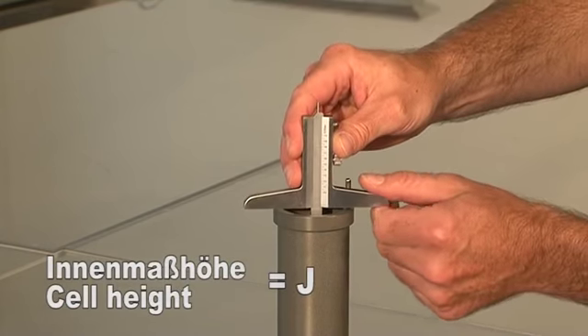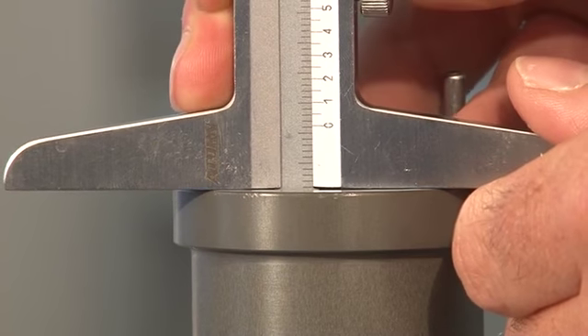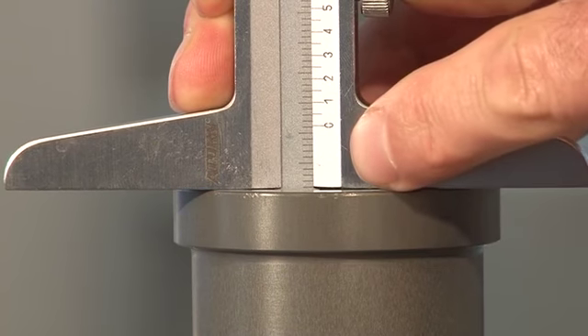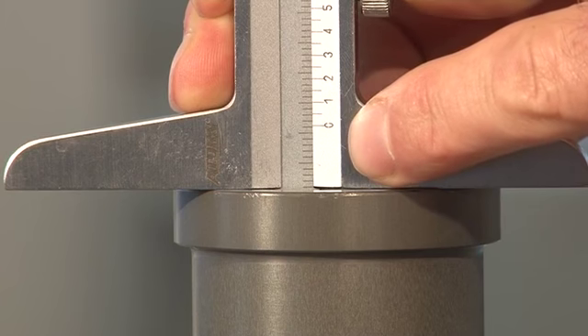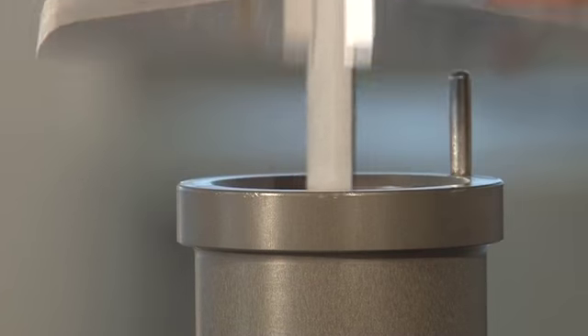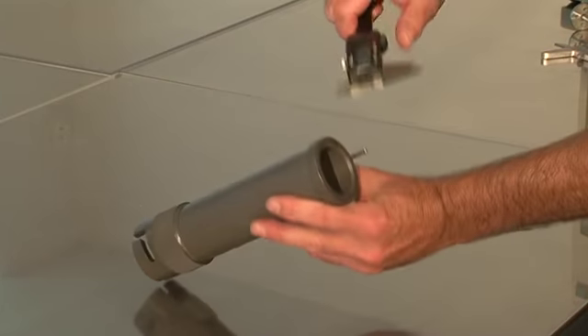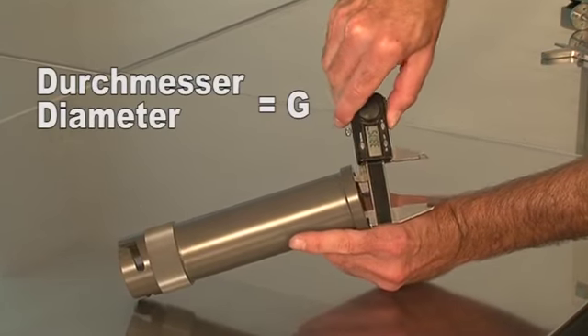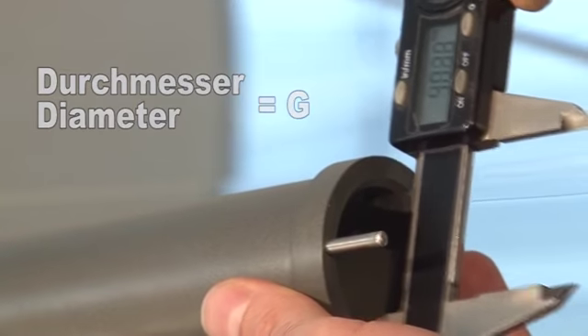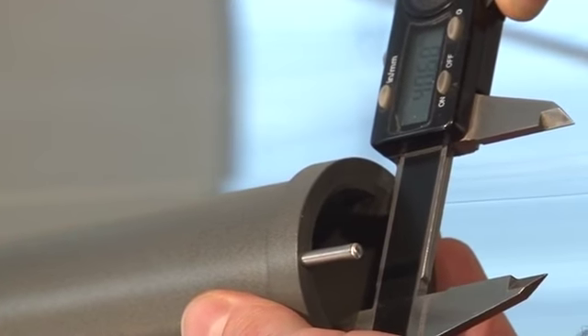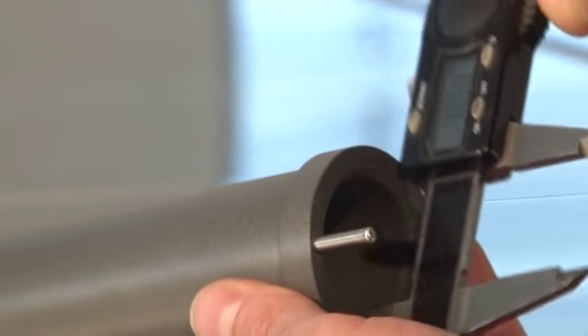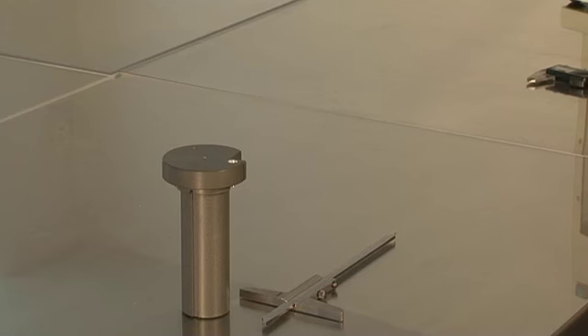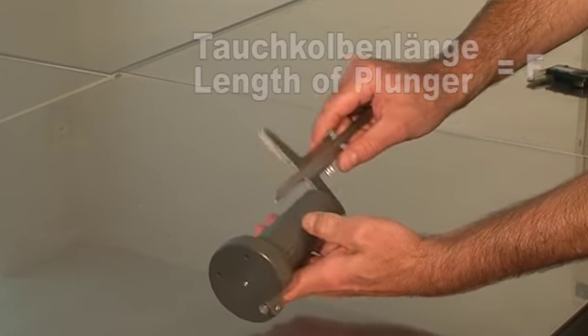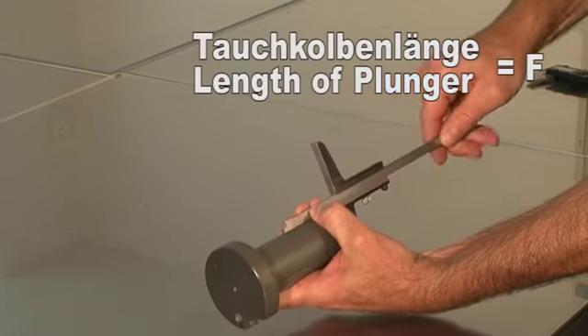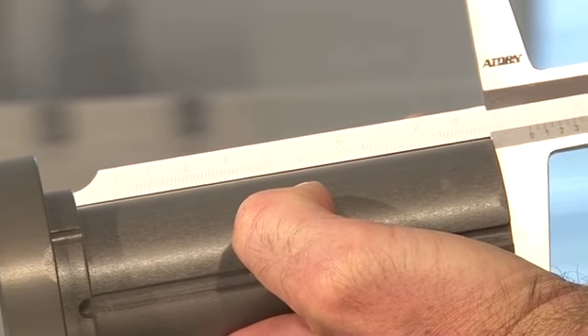All cell dimensions are accurately determined to 1/10 of a millimetre. The depth gauge is used to measure the internal height of the measuring cell at 6 different points and the mean value calculated. Then the diameter of the cell, G, is measured at 6 different points and the mean value is calculated. Finally, the plunger length, F, is determined at 6 different points and a mean value is calculated.